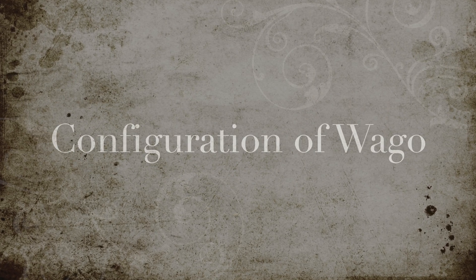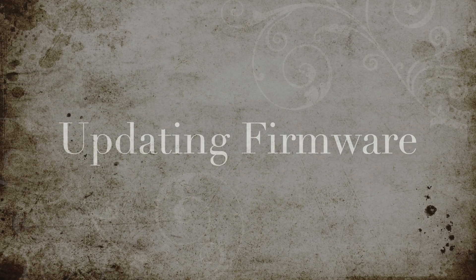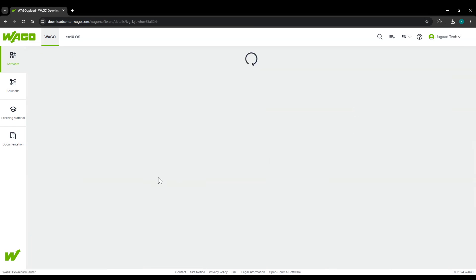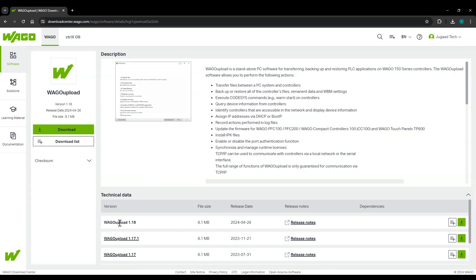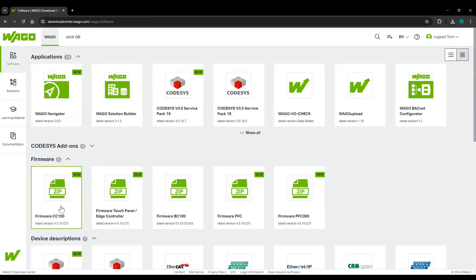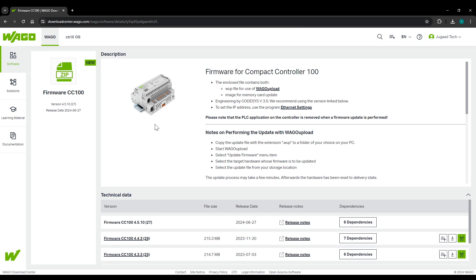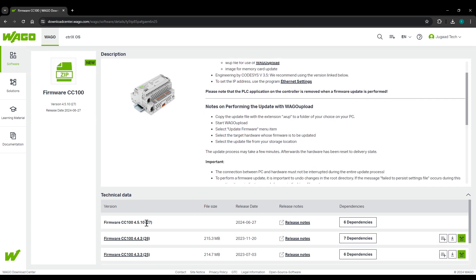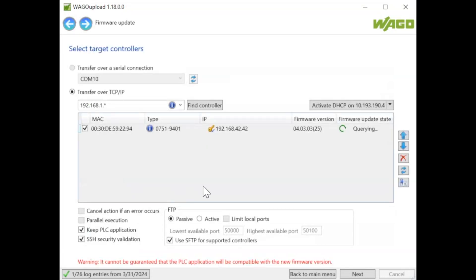This particular controller with universal I/O will be released later this year — it is not yet announced. To configure the WAGO CC100, we will start with upgrading the firmware. To do that, we can utilize the WAGO Upload Tool, which we can download from DownloadCenter.WAGO.com — the latest version — by having your own account. On the same website we can also find the firmware for CC100. Firmware version 27 has not yet been released, so right now I am using firmware 26, which we download and use to upgrade the firmware of the CC100.